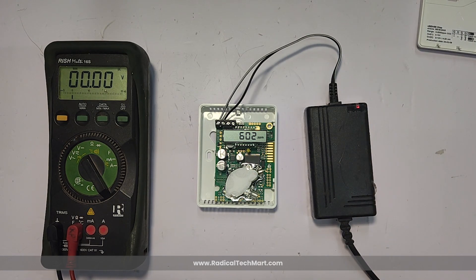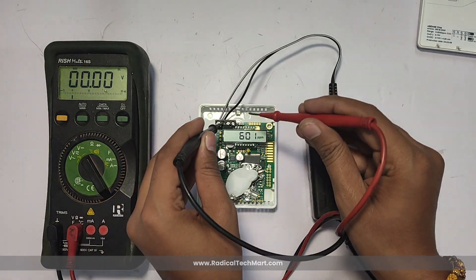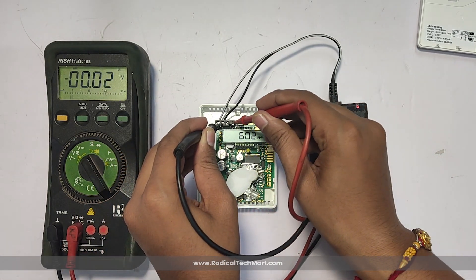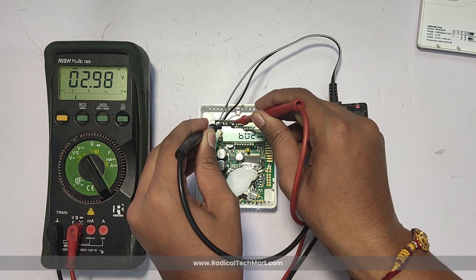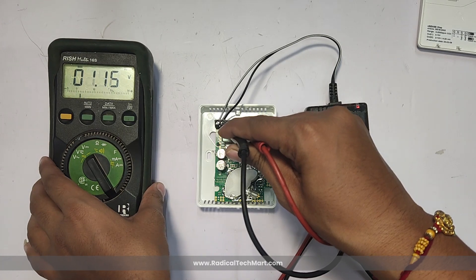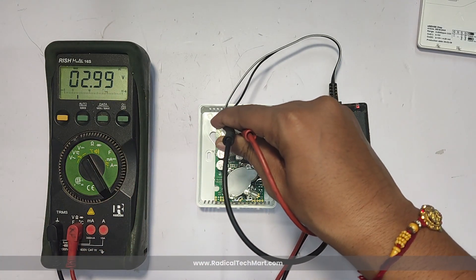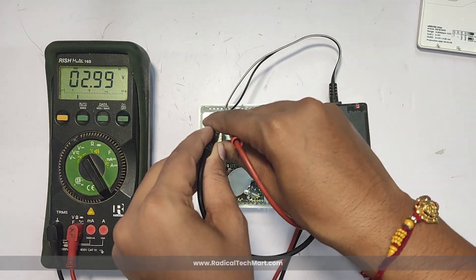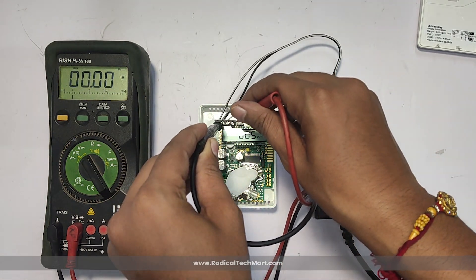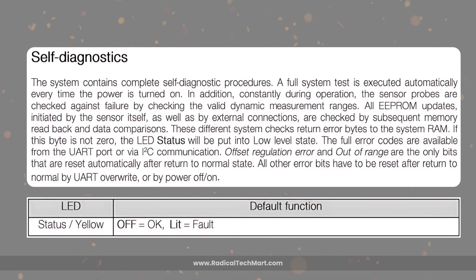During operation, the sensor probes are constantly checked against failure by verifying valid dynamic measurement ranges. All EEPROM updates, whether initiated by the sensor itself or by external connections, are checked by subsequent memory read-back and data comparisons. These system checks return error bytes to the system RAM. If this byte is not zero, the LED status will be put into a low-level state. The LED indicator status descriptions can be seen on screen right now.